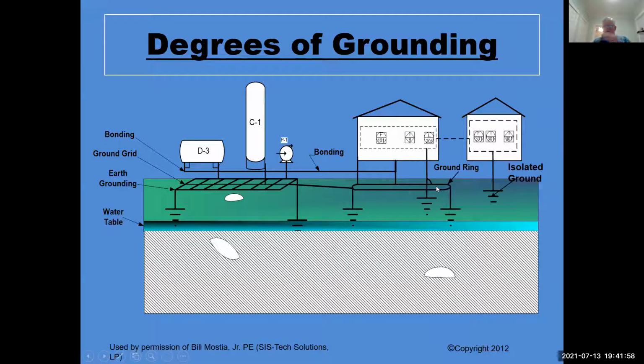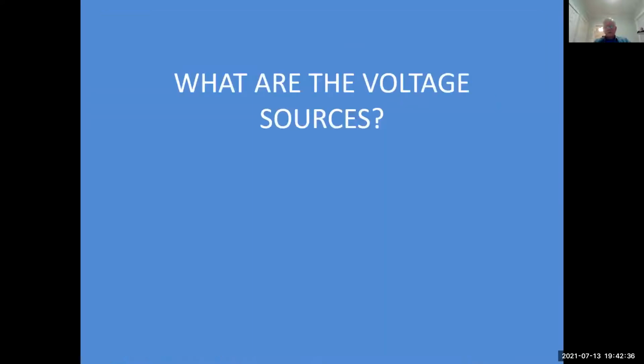The degrees of grounding, you can have your outbuilding with a single ground. You can have ground grids in the soil. It all depends on what you're trying to protect and how much money you want to spend. If you have $50 worth of equipment, you're not going to spend $50,000 to put in a system to protect it. You'll just consider it a consumable. If you get into refineries and things like that, where they have a real problem if there's any arcing or potential differences, they have very elaborate grounding systems with ground grids and so forth, as do electrical substations.